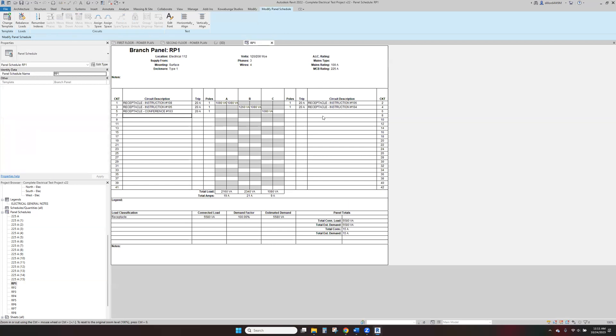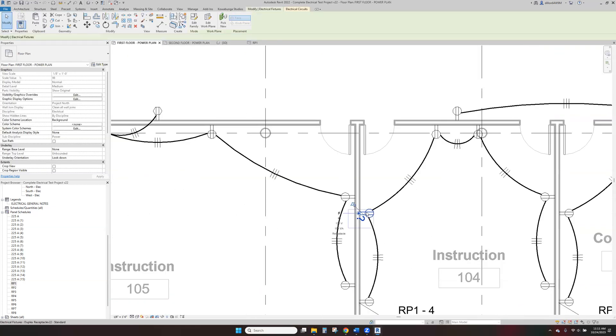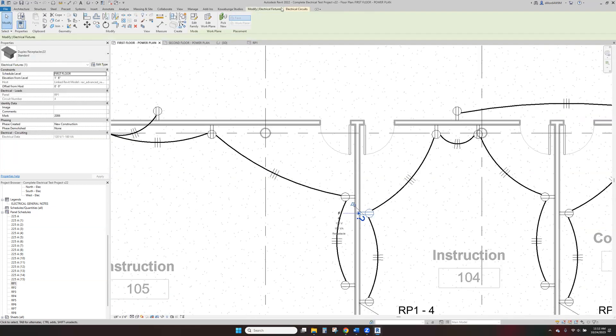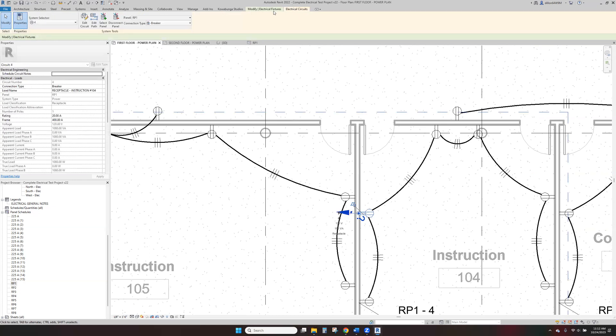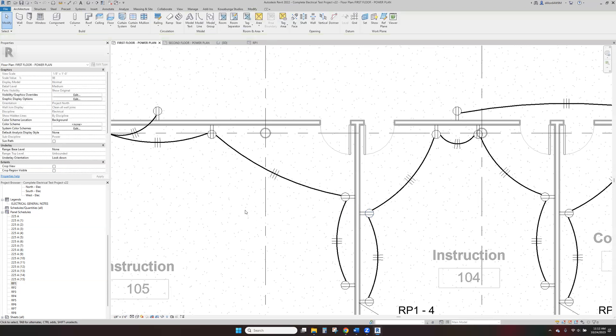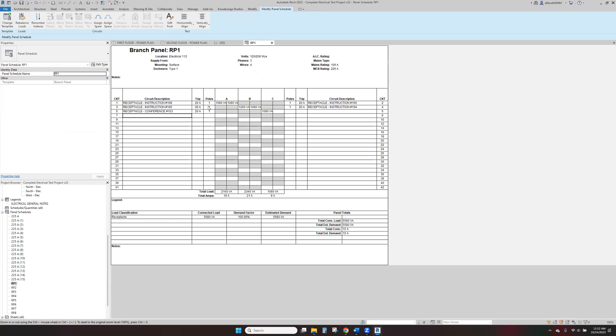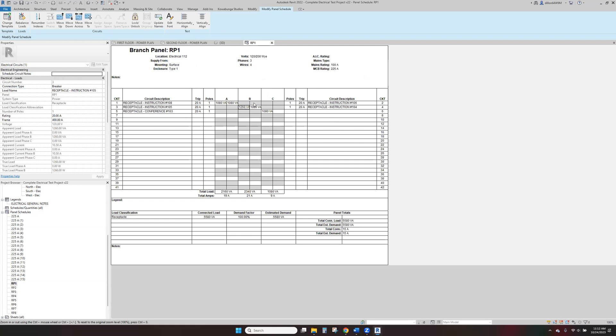So there we go, that's how you do naming of receptacles, really any circuit description within Revit. You can do it either from the panel schedule or you can do it here, clicking on any device that is circuited, make sure you check or click on electrical circuits and then you can change it here. And then change your frame rating, all that kind of good stuff as well in Revit. If you show both amp frame and amp trip settings within your panel schedule. For this one we just show trip, we don't show frame settings for receptacle panels because trip and frame are the same thing. But for your switchboards if you have an amp frame and an amp trip setting you can change that there. And then here's the circuit where we added a couple devices to it and it updated our VA calculation here. So there you have it, that's how to circuit in Revit and change your circuit names.